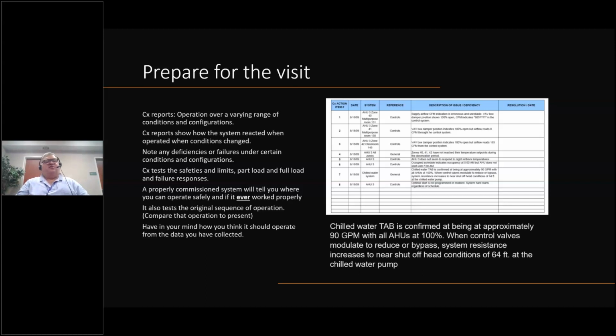A properly commissioned system will tell you where you can operate safely, and whether it ever worked properly. Did this system ever work properly? It also tests the original sequence of operation and compares that to the operation at present. So you could say it was designed or commissioned to operate like this, and then when you get on site, it's operating in a completely different way. You need to have in mind how it should operate based on the data you've collected. You must start thinking in terms of, I think it ought to operate like this - even though they designed it and put it in like that, I think it should be like this. So note that down.